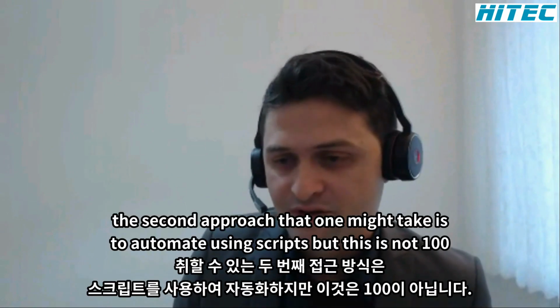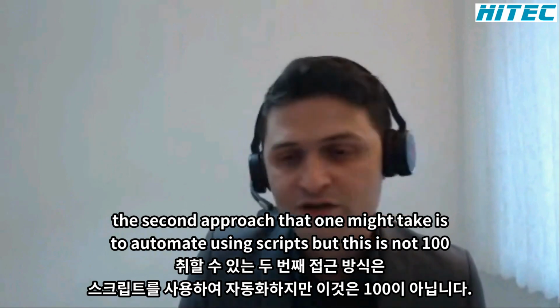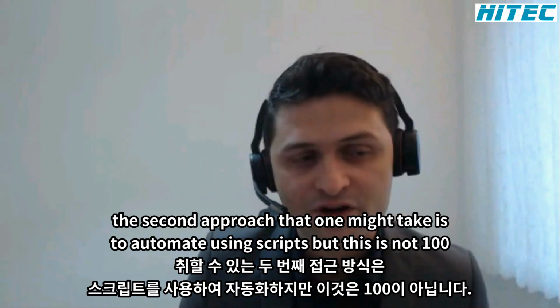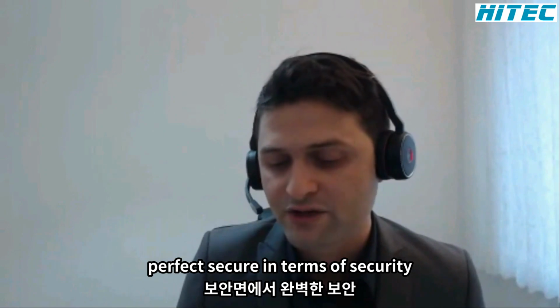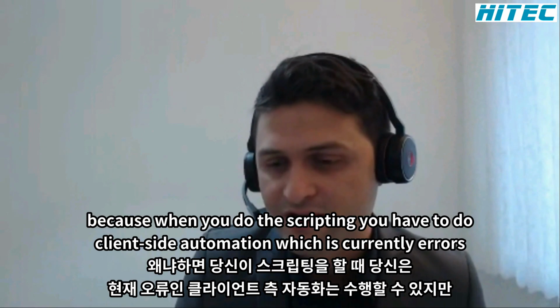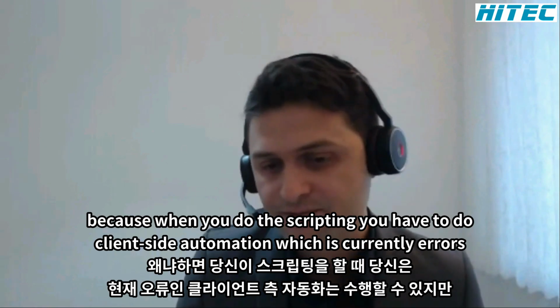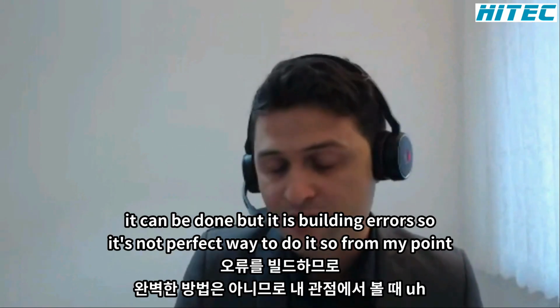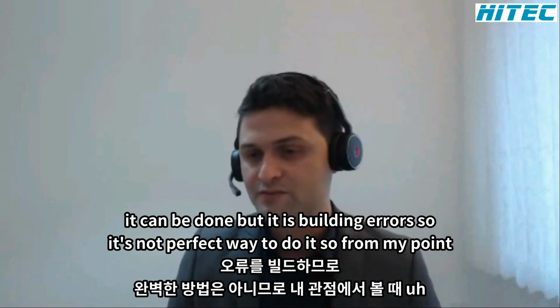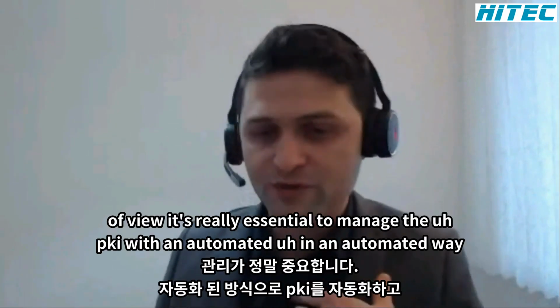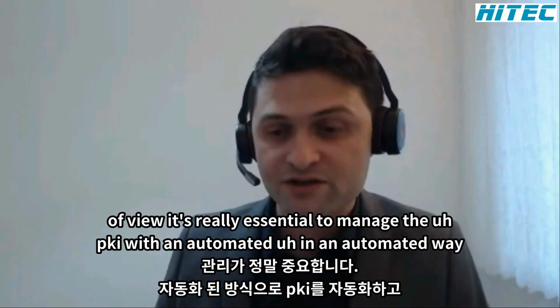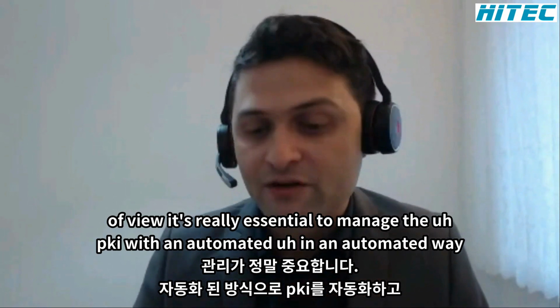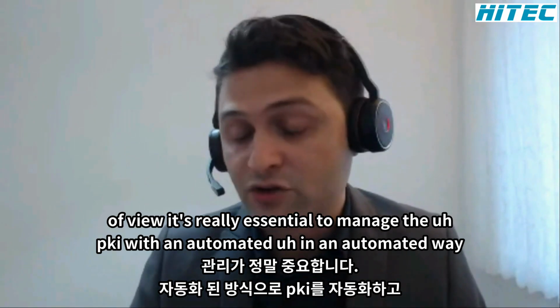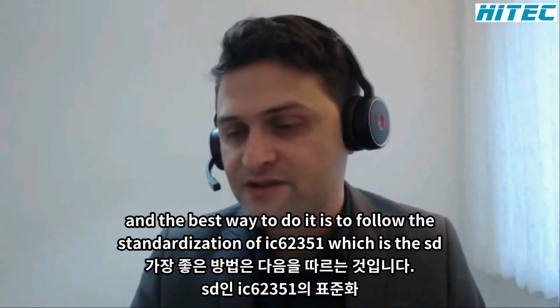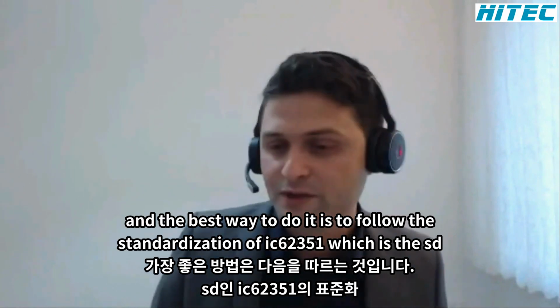The second approach one might take is to automate using scripts, but this is not 100% perfectly secure, because when you do the scripting, you have to do client-side automation, which is prone to errors. It can be done, but it is error-prone, so it's not the perfect way to do it. So from my point of view, it's really essential to manage the PKI in an automated way. And the best way to do it is to follow the standardization of IEC 62351, which is EST.